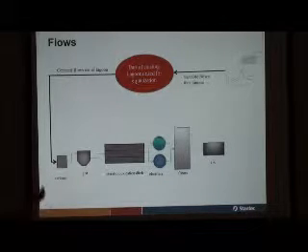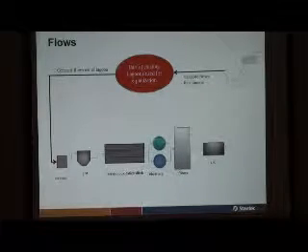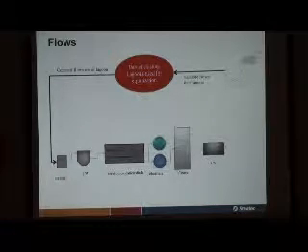So one of the concepts we looked at is that you have existing lagoons out there, and they are a value. They're an asset the municipality has. And what the lagoons can be used for is they can damp out those peak flows. So they actually act as kind of a buffer storage. During the summer months when the flows are high, you can pump out of those lagoons at kind of an average lower rate, and let the lagoons fill up during the summer and draw down during the other portions of the year, which then makes all these little components a lot smaller, at least the ones that are on the front and back end of the plant.